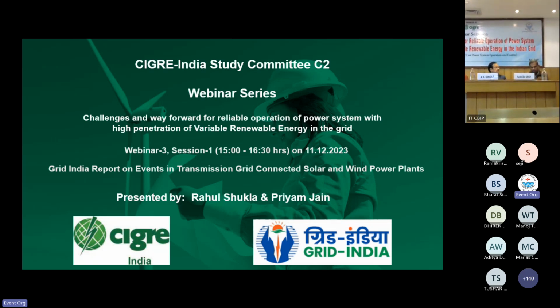the first thing flagged almost a decade back, because suddenly as the frequency crossed 50.2 hertz, the rooftop solar went out of the system. It was a protection setting of the rooftop solar, which is fine if you have only a few megawatts. But we could end up losing much more than the single largest contingency for the entire continental Europe. So that was the first time this aspect of the standard was flagged and the standards revised.